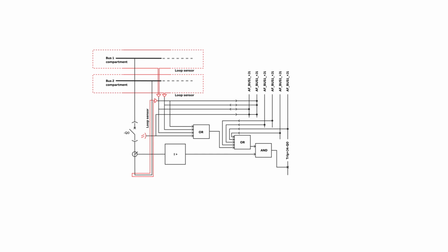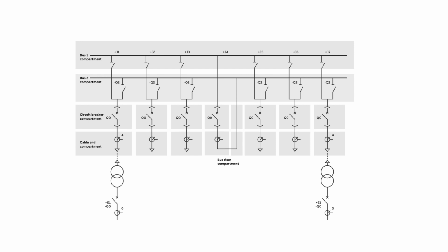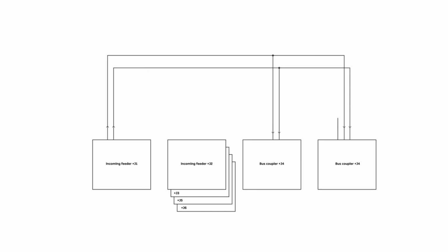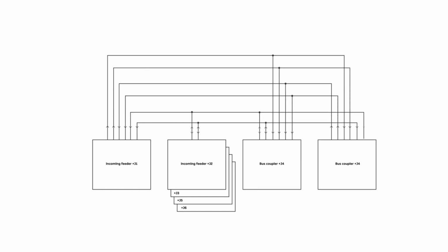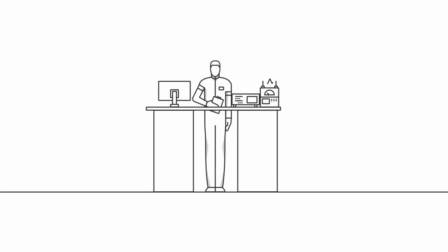SSC600 protection relays. Next up, Matthew starts thinking about the interbay communication to plan the needed protection and wiring applications. To enable the communication between the protection relays, for example, sending and receiving protection tripping commands, you need to connect the relays to each other. This is done either with traditional hardwired signals, in other words, hardwiring, or by utilizing communication protocols. Matthew's protection scheme is now ready, and it is clear that building the system needs a lot of interbay wiring and engineering effort.